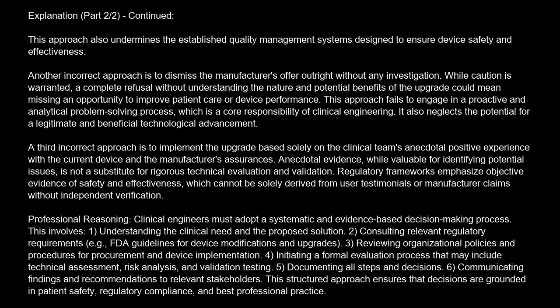Another incorrect approach is to dismiss the manufacturer's offer outright without any investigation. While caution is warranted, a complete refusal without understanding the nature and potential benefits of the upgrade could mean missing an opportunity to improve patient care or device performance. This approach fails to engage in a proactive and analytical problem-solving process, which is a core responsibility of clinical engineering. It also neglects the potential for a legitimate and beneficial technological advancement.